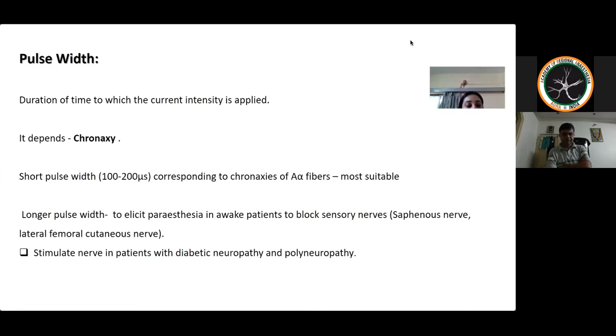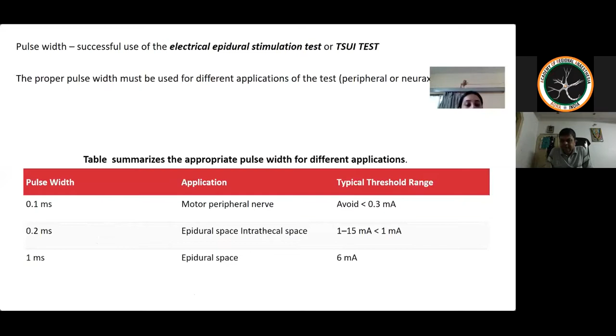Now, pulse width also has a role in the successful use of the epidural stimulation test. In this table, the different pulse widths, threshold ranges, and their applications are given. For a pulse width of 0.1 millisecond, a current amplitude of not less than 0.3 milliampere is used in the motor peripheral nerve. With a current intensity of not less than 1 milliampere and a pulse width of 0.2 milliseconds, they are used in the epidural space and intrathecal space, whereas a current intensity of 6 milliampere and a pulse width of 1 millisecond are used in the epidural space.